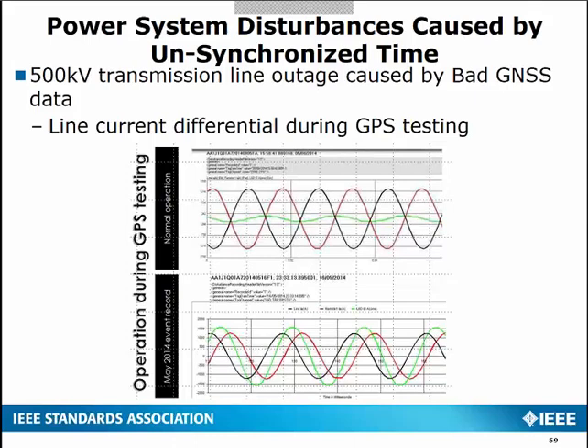In this case, it led to the data between both ends of the line being unsynchronized. If you look at the top graph, that's a normal load operation. You have the currents from the local end and the remote end, the red and the black signals, being 180 degrees apart with a little differential. A little differential is normal with the line charging current of any transmission line.